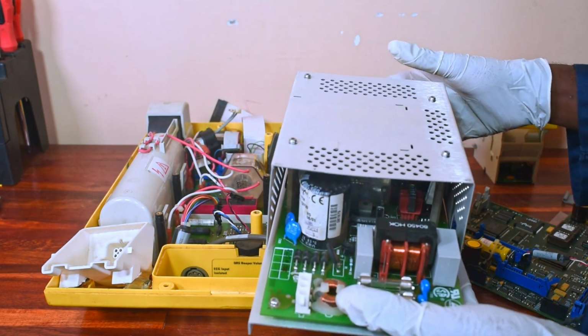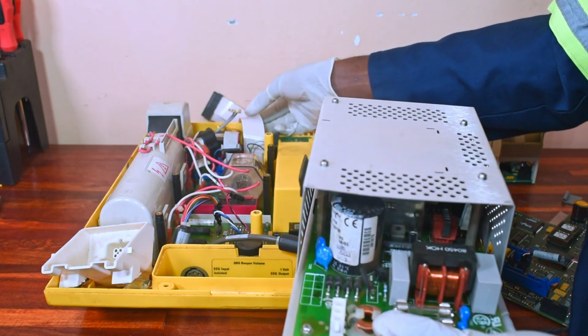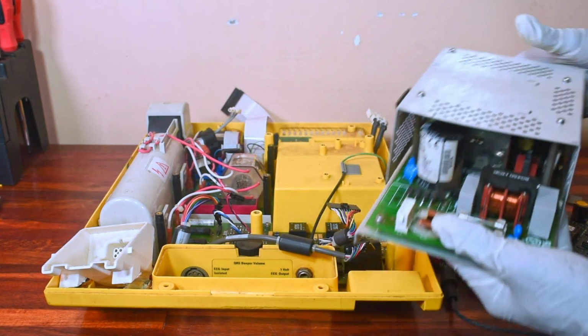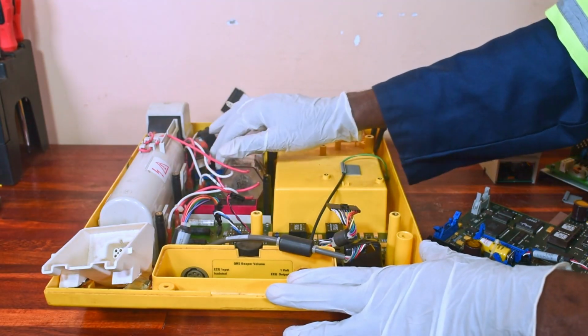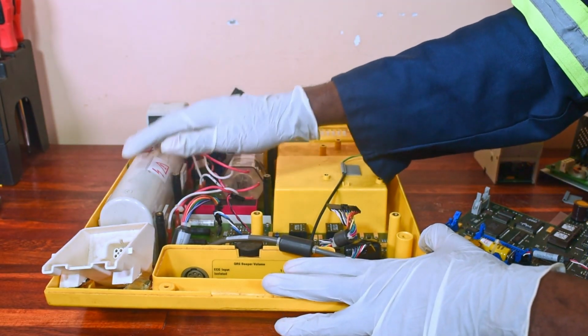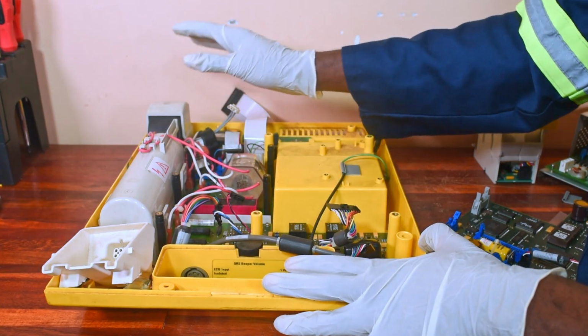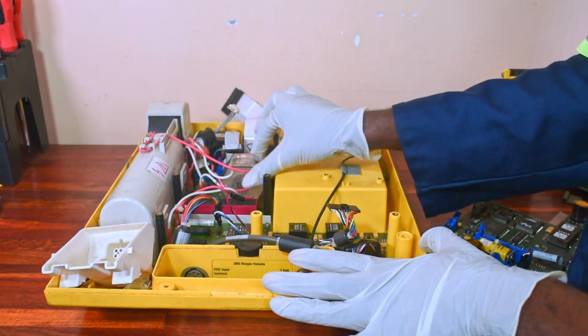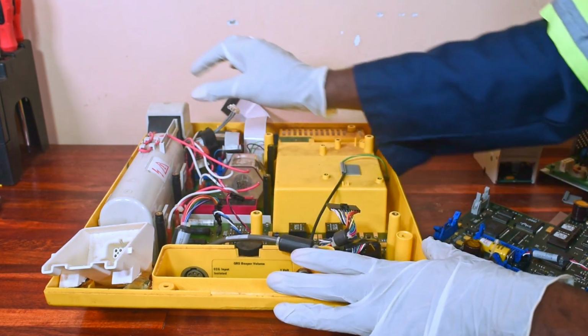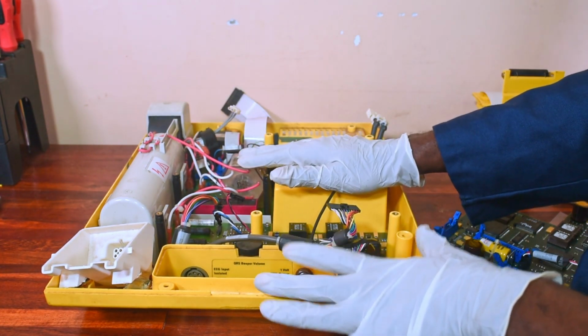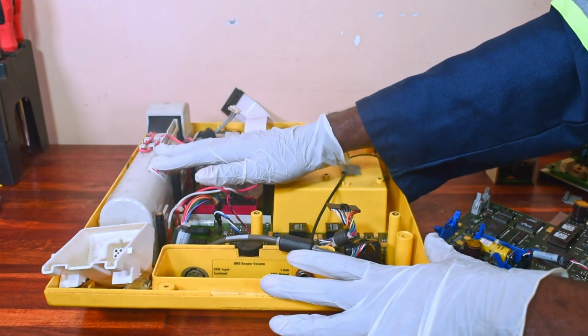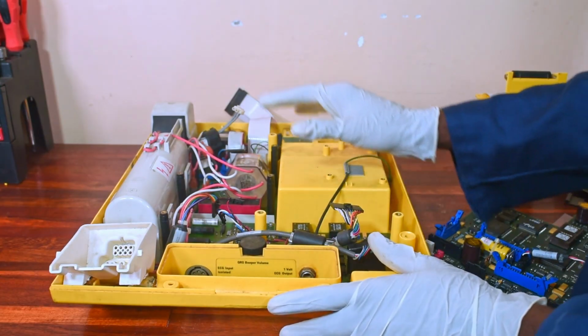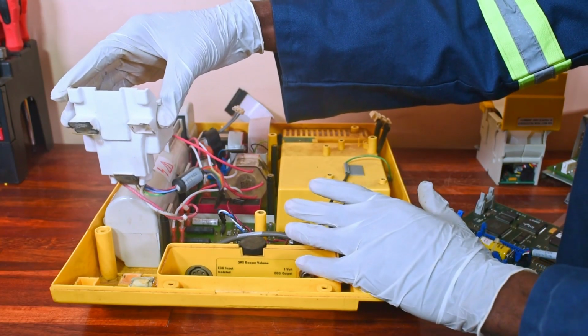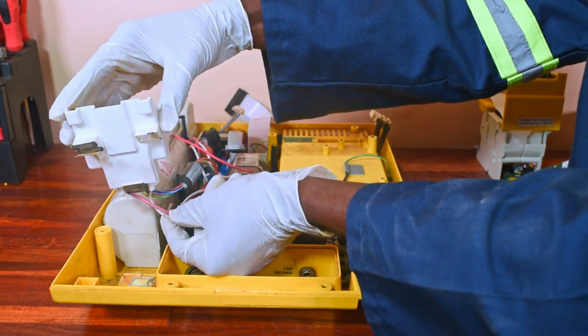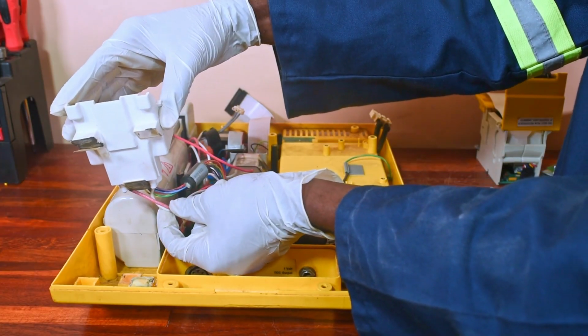The power supply is also interfaced with the high voltage control board through this cable. From the high voltage control board, power is supplied to the high voltage capacitor and the patient inductor. The switching of high voltage to these components is controlled by this patient relay. Together with the patient inductor, the patient relay controls the charging and discharging of the high voltage capacitor. Electrical energy is delivered from the high voltage control board to the defibrillator connector through the ECG front end board. And these two right here are the cables that deliver electrical energy to the connector.